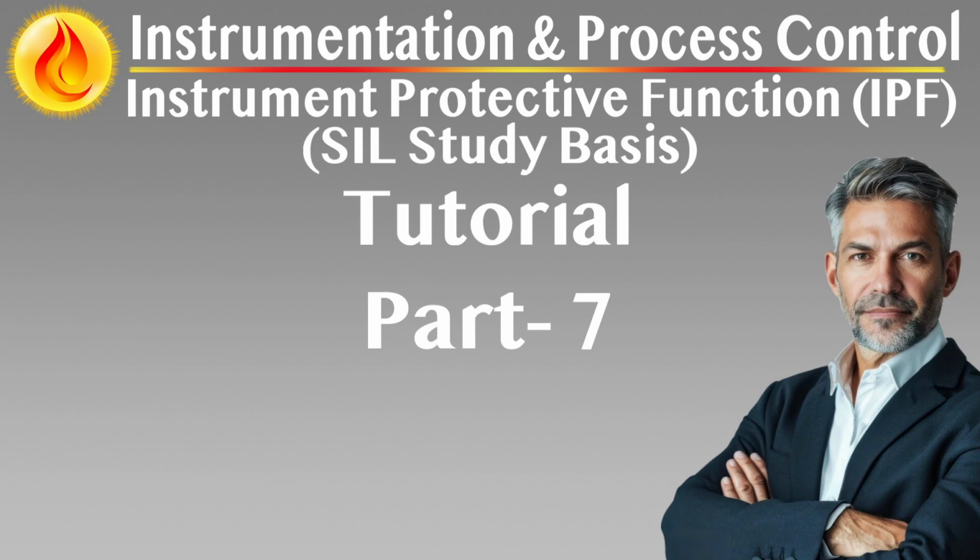Support maintenance and continuous improvement. Use test outcomes to refine failure rate assumptions, maintenance strategies, and diagnostic methods. Types of IPF testing: proof testing, periodic test of the complete IPF to reveal undetected dangerous failures, typically performed offline or under controlled plant conditions depending on process criticality and safety impact.